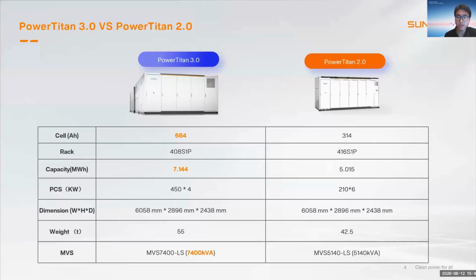And from this slide, we can see the comparison between Power Titan 3 and Power Titan 2. First, let's look at the battery cell technology. For Power 3, we adopt a 684 ampere-hour large capacity cell, and for Power 2, we use a 314 ampere-hour cell. And thanks to the large cell capacity and the higher integration level, the energy capacity of Power 3 can now reach 7.144 megawatt-hour, while Power 2 can provide around 5 megawatt-hour. And we also increased the PCS size from 210 kilowatt to 450 kilowatt. After this slide, I will introduce the highlights and the functions of our Power 3 product.